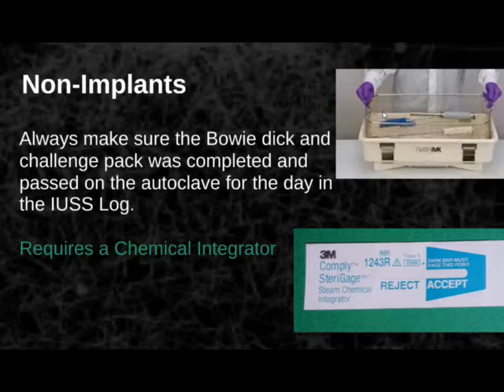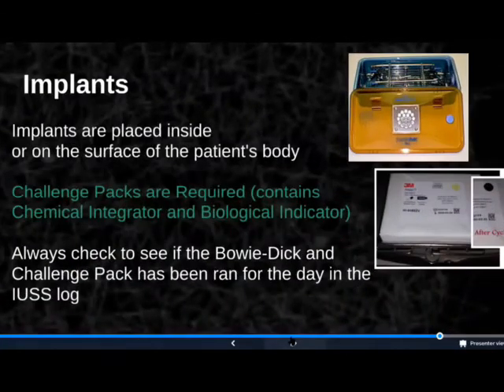And hopefully it's not a hemostat, by the way. But anyway, moving on, always make sure that the Bowie-Dick and the challenge pack has ran for the day before you use the autoclave. And a non-implant only requires the chemical integrator. We just need to know if it accepts or rejects, because this instrument or item is not going to stay inside of the patient. They are not going to leave with the patient. It's going to be put back with the tray, etc.